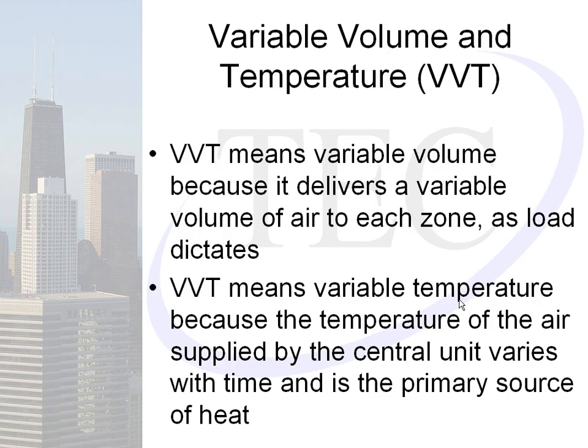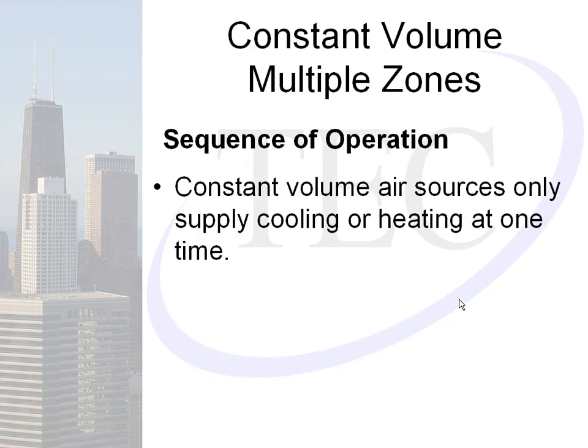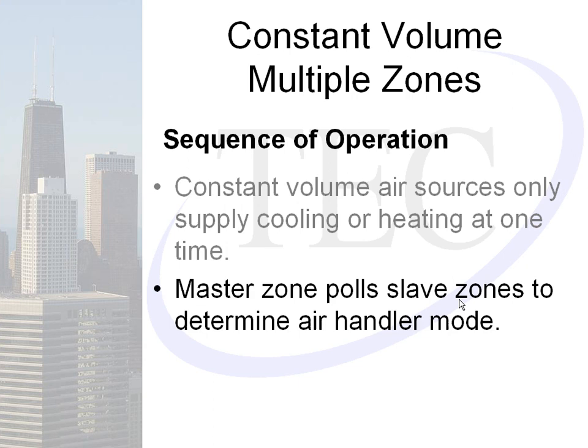VVT stands for variable volume, variable temperature. It's variable volume because it allows the volume of air to be distributed as necessary per zone. Variable temperature means the rooftop can switch between heating and cooling, unlike a VAV system where the rooftop is in cooling mode constantly. The sequence of operation: the master zone polls all slave zones to determine the current mode of operation demand, tells the rooftop which mode to operate in, and the rooftop unit turns on and provides that level of air.